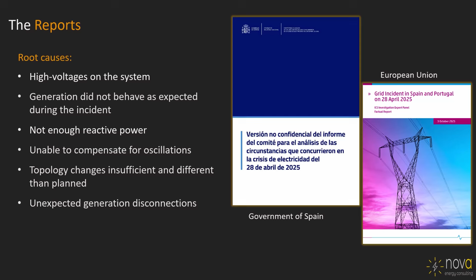Then also finally there was this aspect of generators disconnecting that we were not expecting to disconnect. The report, in Spanish, calls it a multifactorial root cause, meaning a little bit of everything happened. It's really hard to say one thing caused the whole collapse. There are certainly contributing factors, and these would be the major causes, but unfortunately it's often the case that there's not a silver bullet. There's not something where you could say, if we put effort and money into this one thing, everything's okay now. That thing doesn't exist.